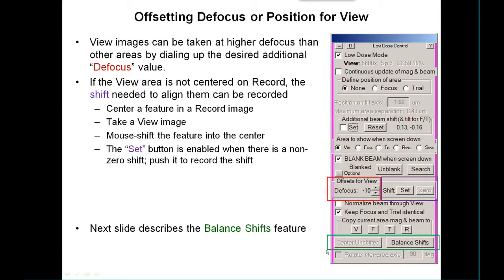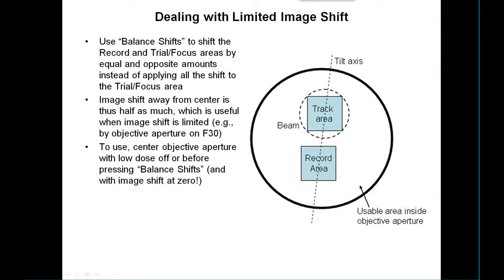Next slide, we're going to talk about the balance shifts feature. What this is to deal with is a problem of having limited image shift. So suppose for some reason you can't shift beyond a certain point, either because the objective aperture comes in or you haven't got much image shift range on the microscope.